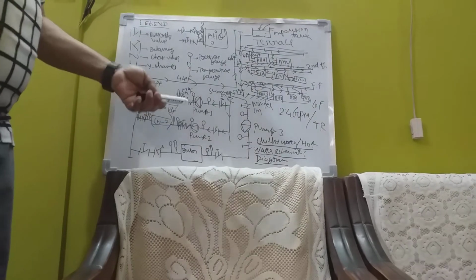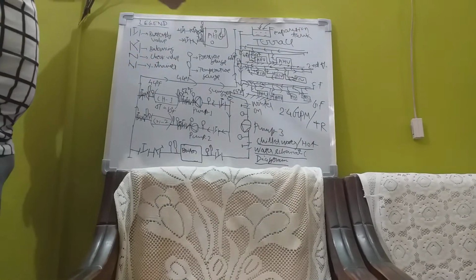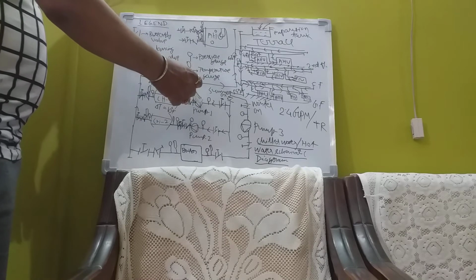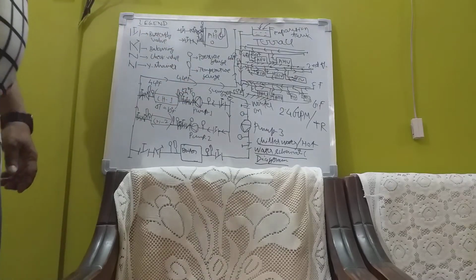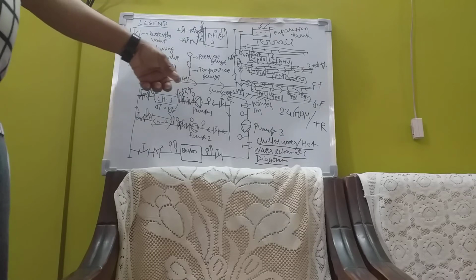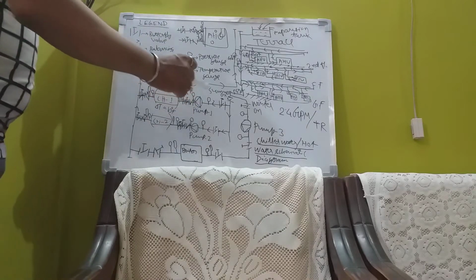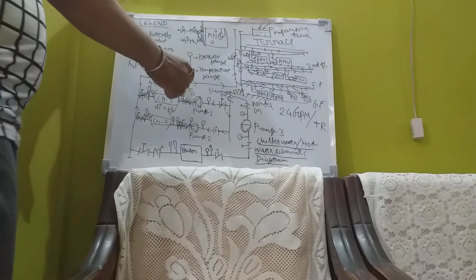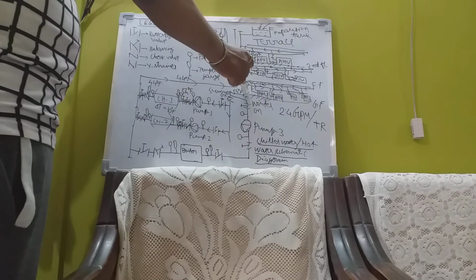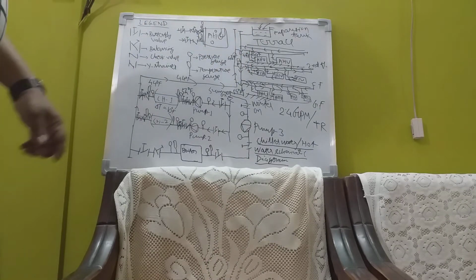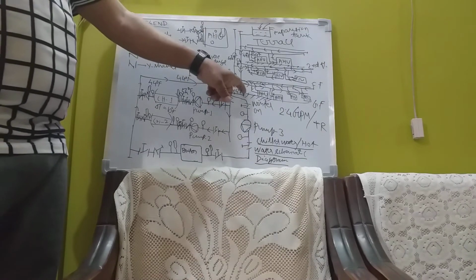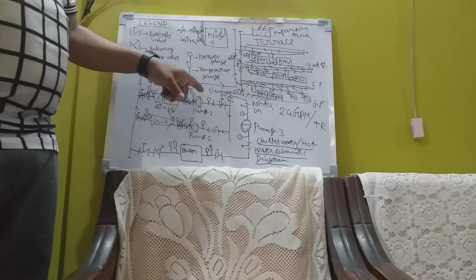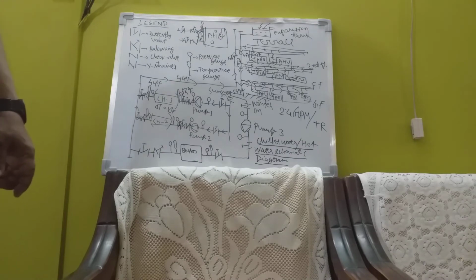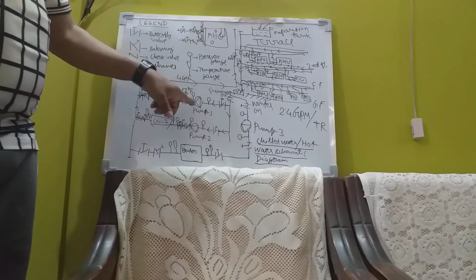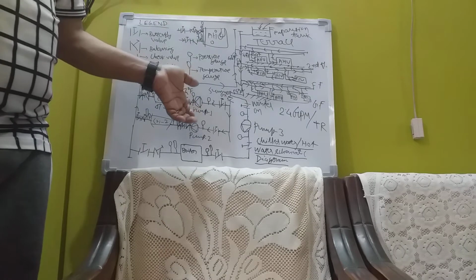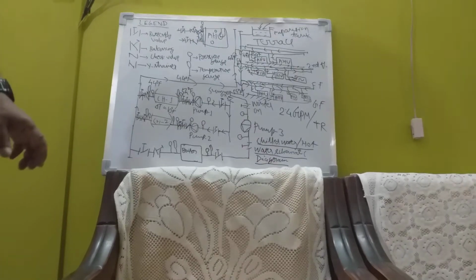Now there are many other value additions to this, like we can put a VFD, that is a variable frequency drive, on the pump. This variable frequency drive actually controls the speed of the pump. How does it control the speed of the pump? It takes the overall temperature reading here. Depending on the temperature reading, high or low, it modulates the pump speed accordingly. And as it modulates the pump speed, at a low speed less power is required to run the pump, and you save power.